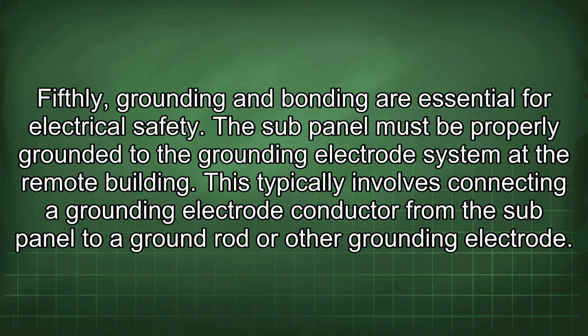Fifthly, grounding and bonding are essential for electrical safety. The sub-panel must be properly grounded to the grounding electrode system at the remote building. This typically involves connecting a grounding electrode conductor from the sub-panel to a ground rod or other grounding electrode.